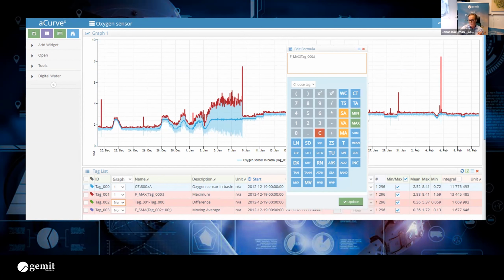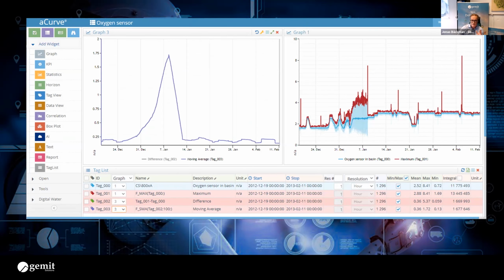And in this platform, you can add an extra time series just with the maximum values. And that can be done with the calculator as shown in this slide. And after a couple of calculation steps where we end with a traditional moving average to remove signal spikes, we finally receive a very clear shark fin. And the shark fin is our created soft sensor.